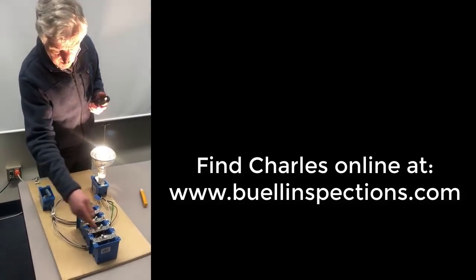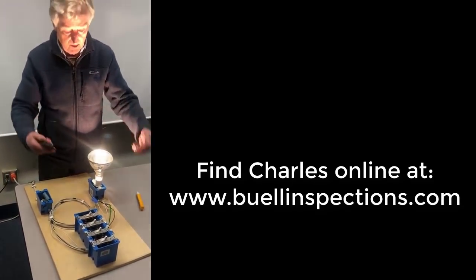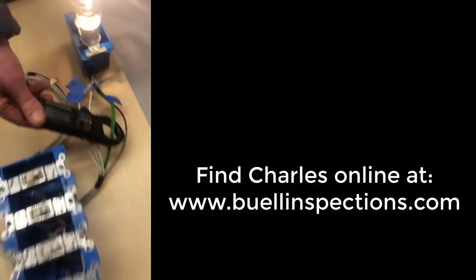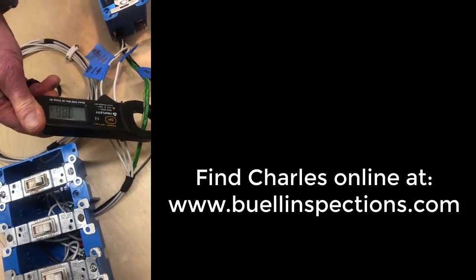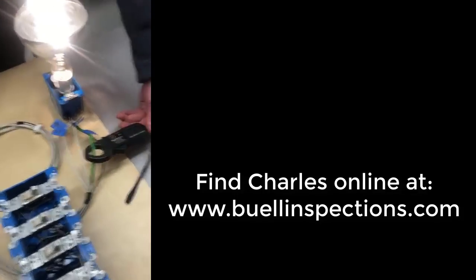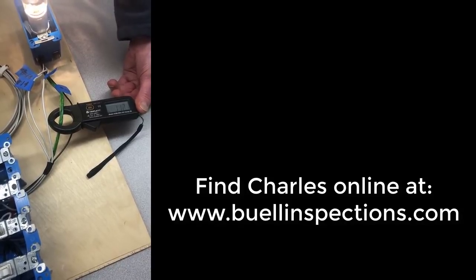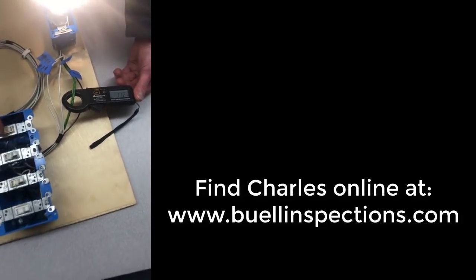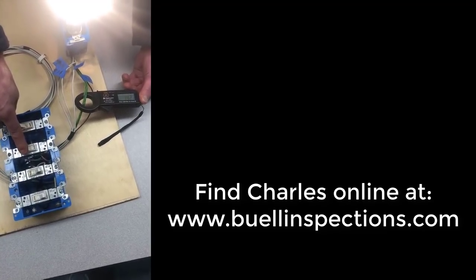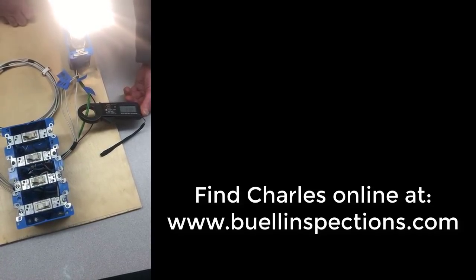Now I'll turn on the 10, and we'll see that the biggest percentage of the current is going to flow on the bare ground wire. What do we got? 0.86. So watch what happens to that 0.86 as I turn off some of the other paths. See how it's going to jump up a little bit more? If I get rid of the other 14, it jumps up even more. It's all going back on that bare ground.